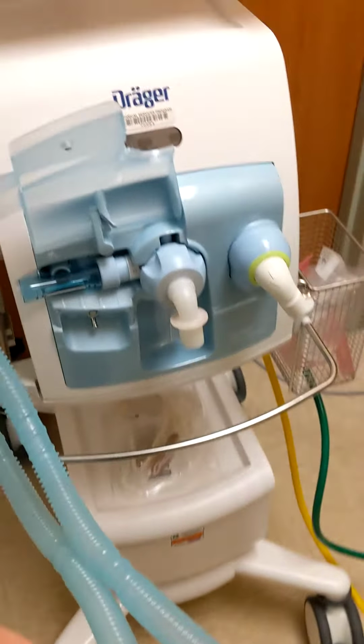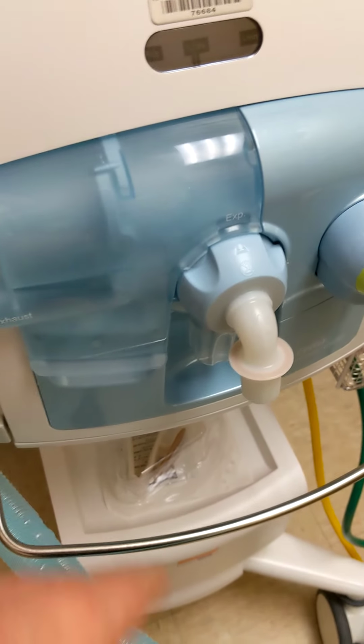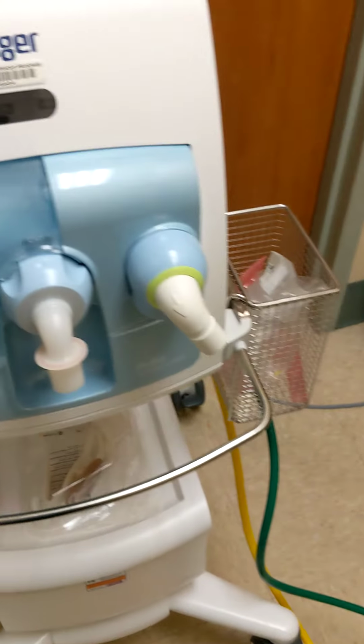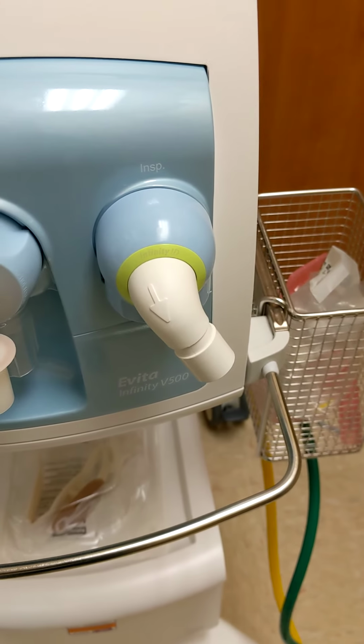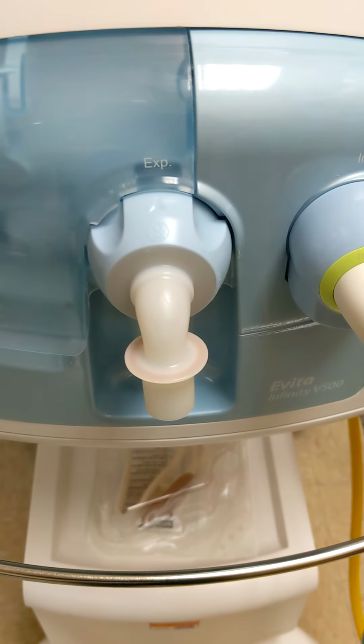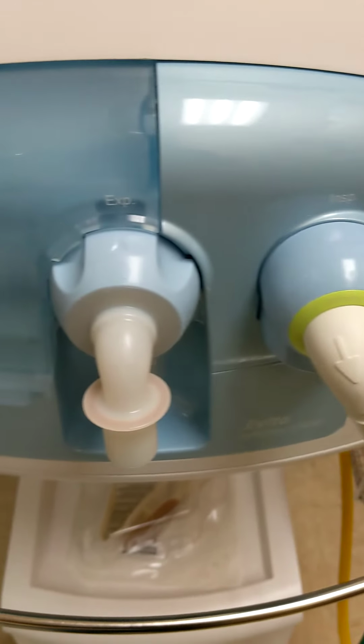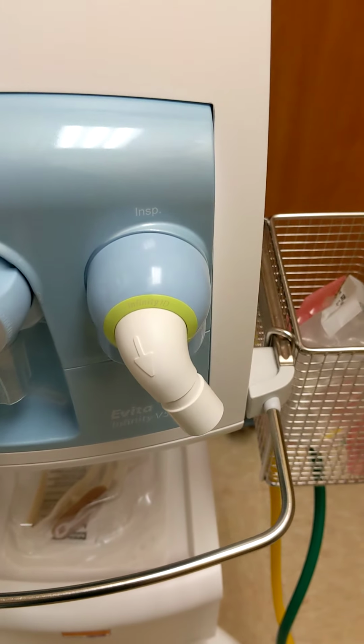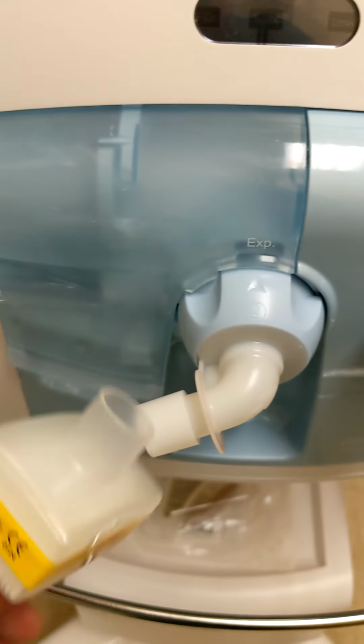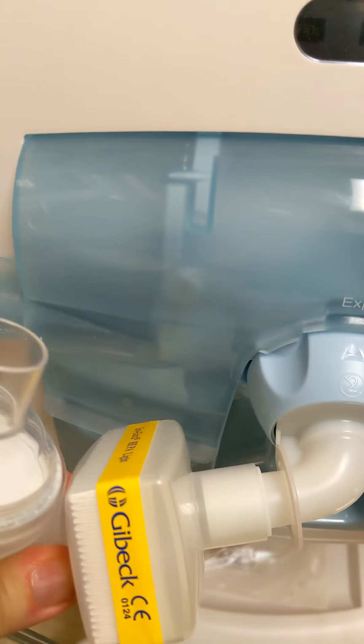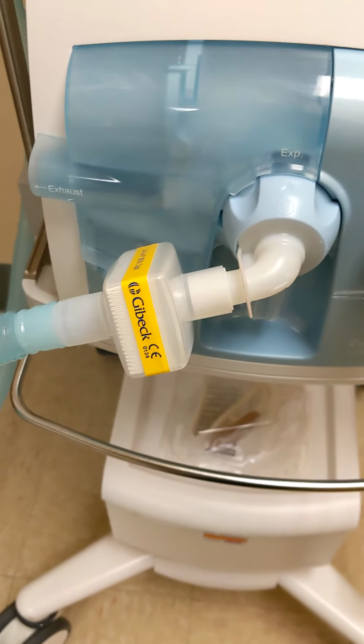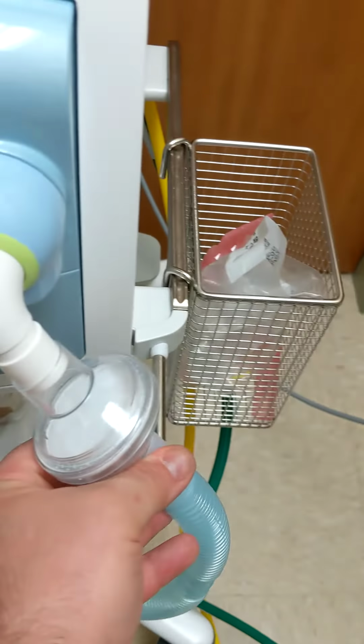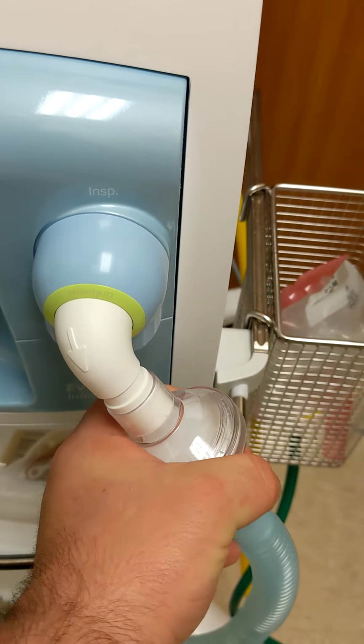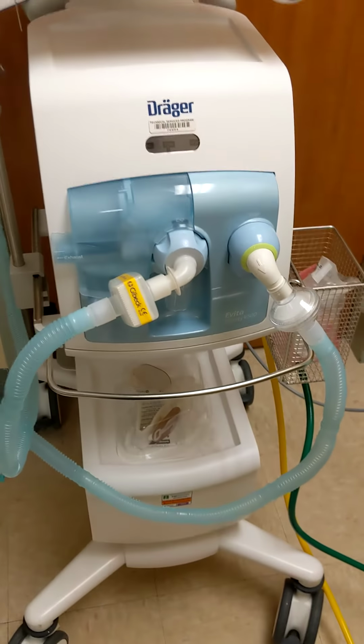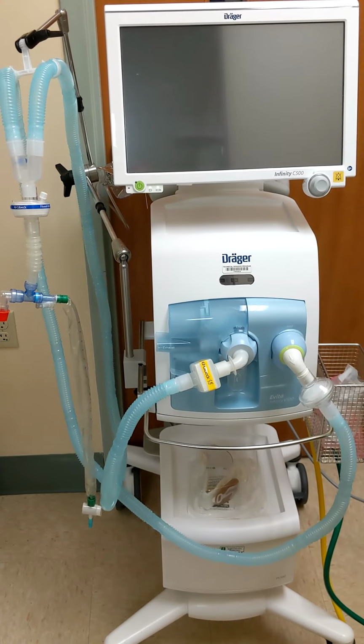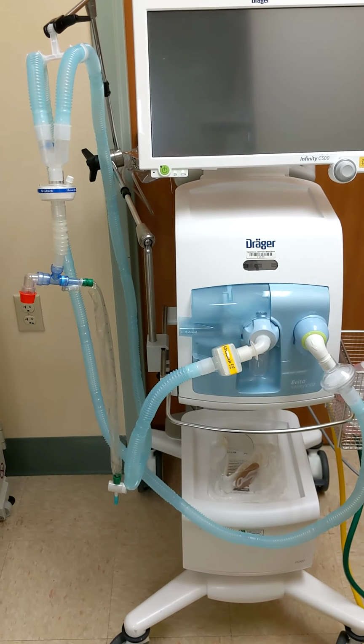So once you have that assembled, flip down your little cover. Remember, green is inhalation, and then expiratory. So inspiratory, expiratory. You're going to put the expiratory circuit with the HEPA filter. The other end is your inspiratory limb. That will conclude how to set up the vent circuit.